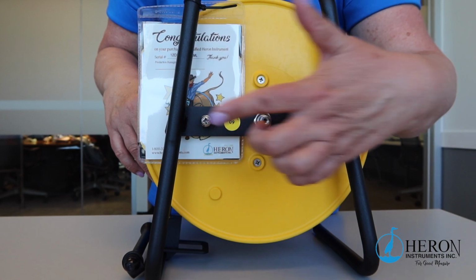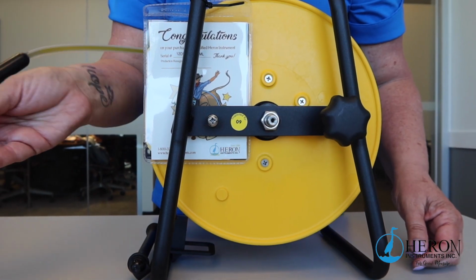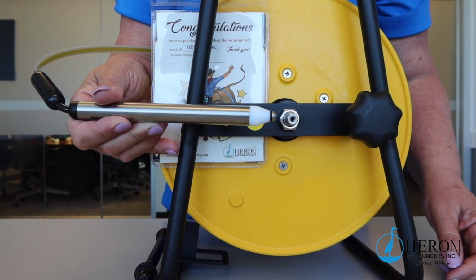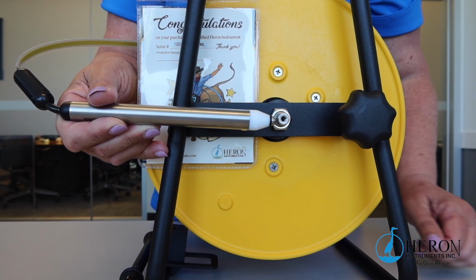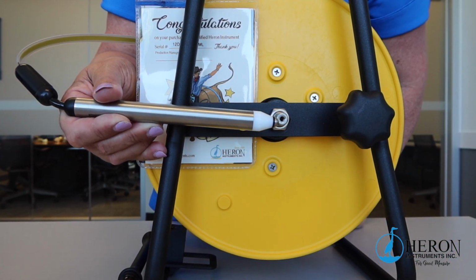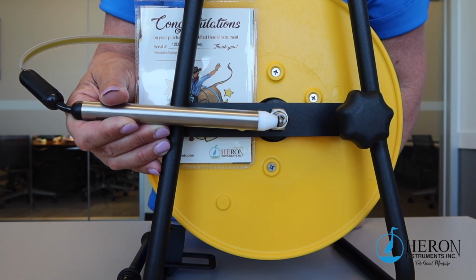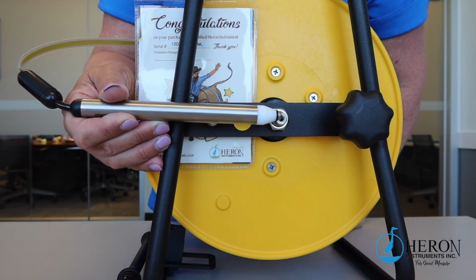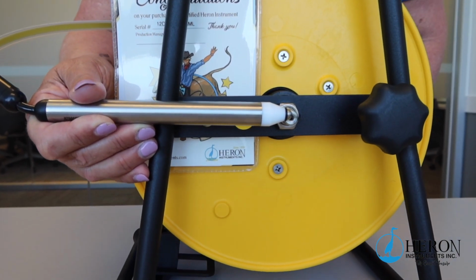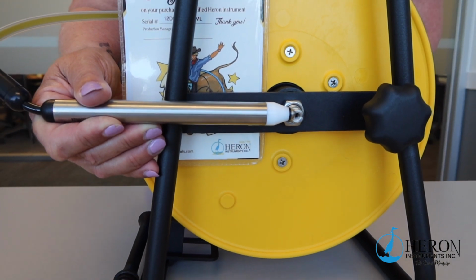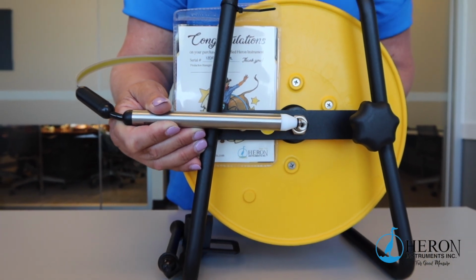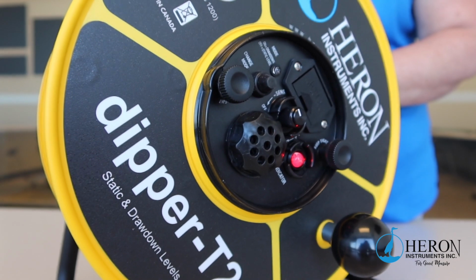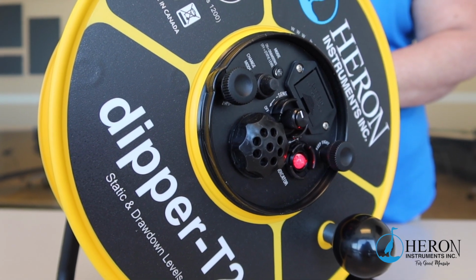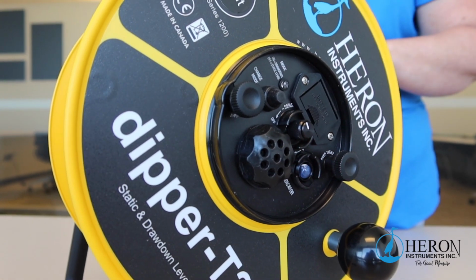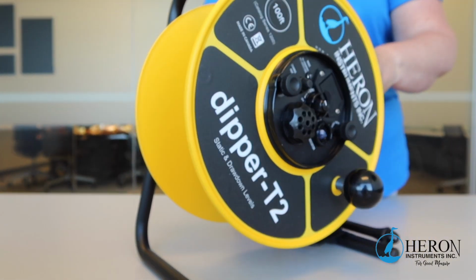Before you go out in the field, we suggest testing the unit to make sure everything is working properly, including the battery power level. Hold the probe tip to the center shaft and the body to the screw at the same time. This will complete the circuit, sending the signal from the probe up the tape to the electronic panel. The buzzer will sound and the LED lights will turn on. We suggest you always carry an extra 9-volt battery in your backpack, just in case.